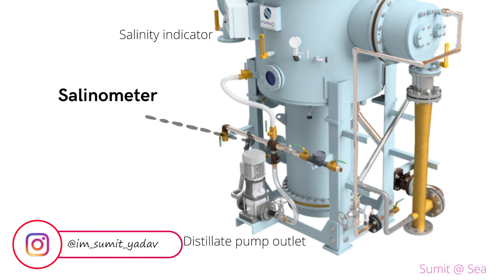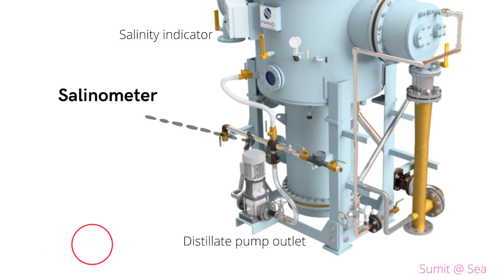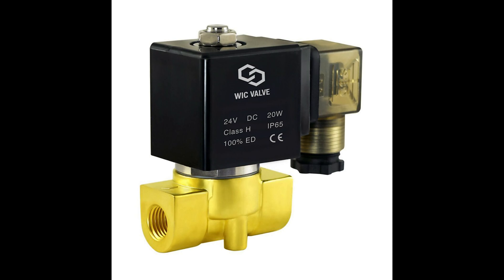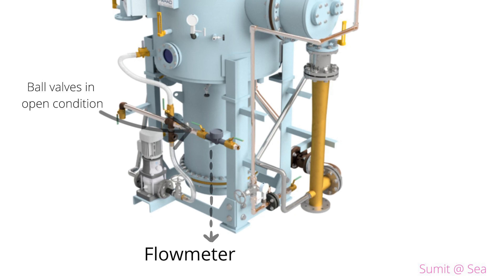Number six is the salinometer — a device installed on the fresh water generator capable of detecting even the slightest salt content in the sampling water. It is connected to the distillate output just before the solenoid-operated three-way valve. The salinometer output feeds to the control panel, which, based on the required salt limit, will send fresh water for storage or back to the fresh water generator. Number seven is the solenoid valve, which opens to return high-salinity distillate back to the evaporator. Number eight is the flow meter, which tells us the actual fresh water production per day or per hour.